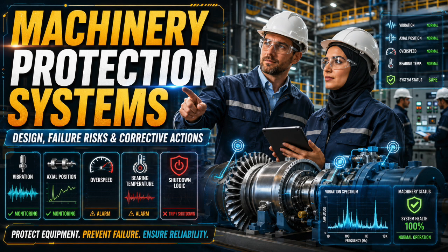For relays, you need contact verification. For bypasses, you need indication verification. For communication, you need data verification. For shutdown, you need cause and effect proof. For integration with control systems, emergency shutdown systems, machinery diagnostics, and operator displays, you need functional confirmation. A correct screen does not prove a correct trip. A correct monitor value does not prove relay action. A correct relay action does not prove the final element responds. Testing must follow the complete chain, and documentation must capture the result.